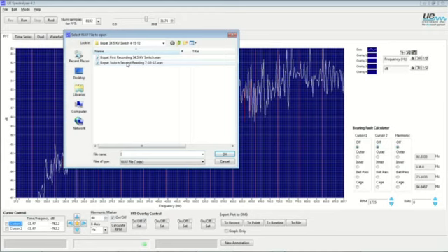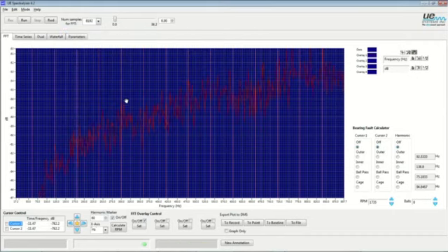The decibel level tells us one thing and one thing only: how close are we to the source of our emission as we are making our recording? The severity is gauged by the frequency analysis and the content in the time domain. And I'll get into that a little bit further, but right now let's see if we have similarities in these two recordings. As I open the new WAV file, you'll notice the overlay turns red, and I will run the next WAV file on top of that.